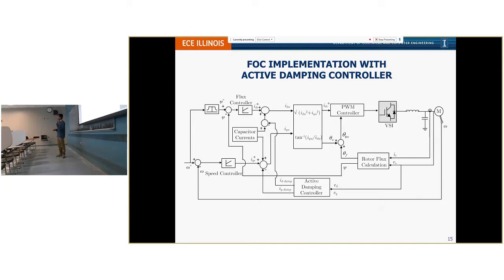Because you would see that the resonance is much more pronounced. And if you use a very high value, you might not even get sufficient damping. So there has to be an analysis of how the damping resistance needs to be selected.